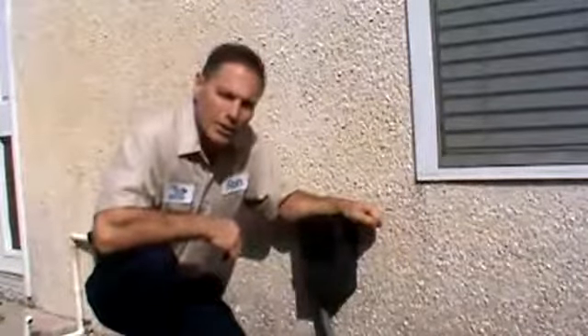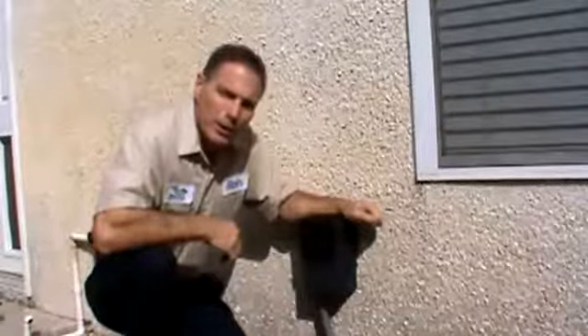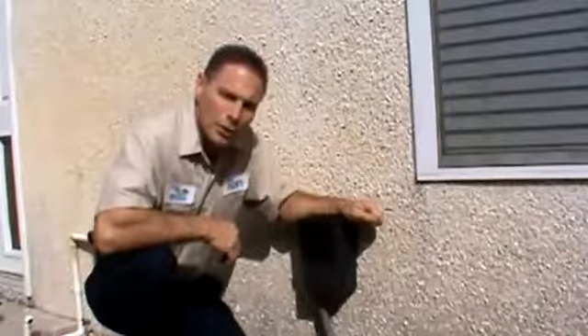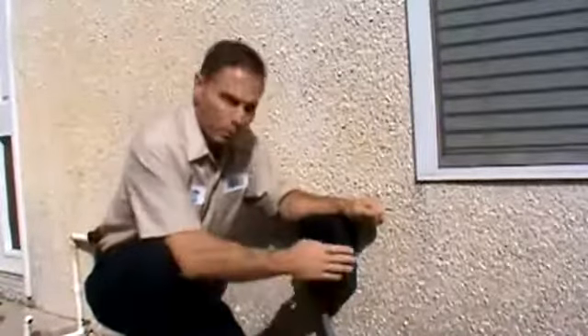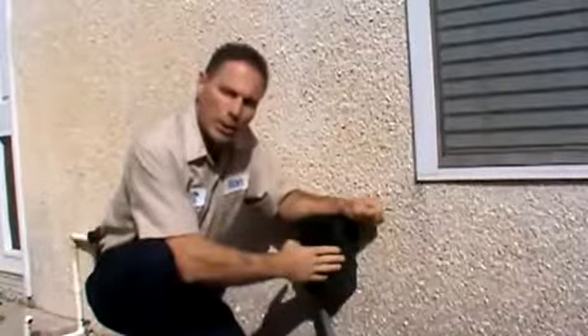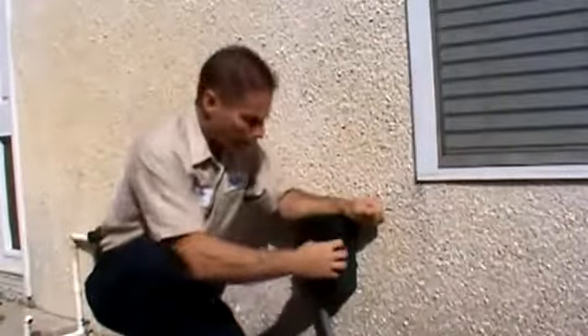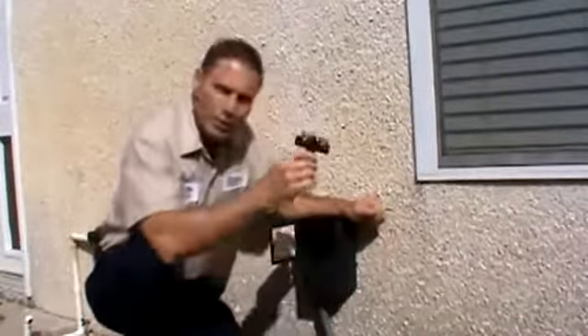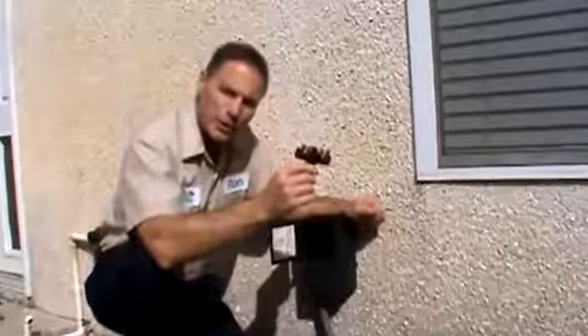Before you check out any component on an air conditioning system, you're going to want to make sure that you're doing it safely. So when we check out the capacitor, you're going to want to turn off and de-energize the power to the outdoor unit. Most of the outdoor units are going to have a disconnect box such as this. This is a more modern one. You can just pull the disconnect out, it de-energizes the power.